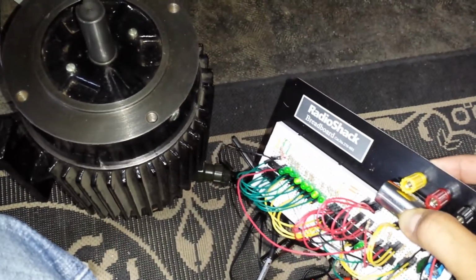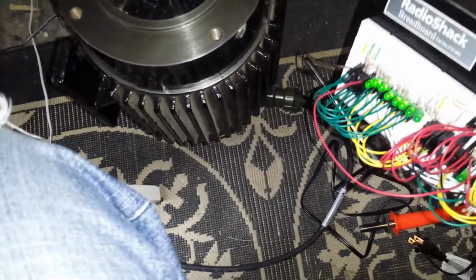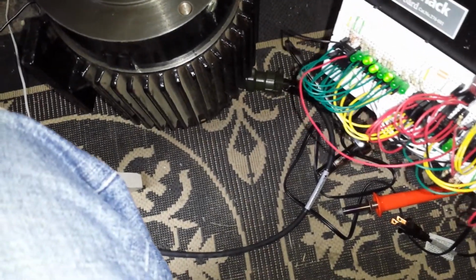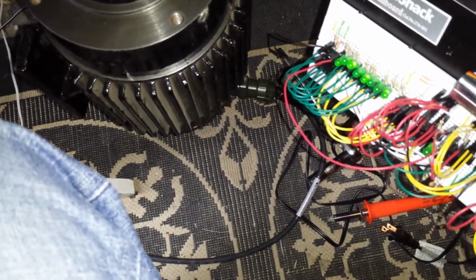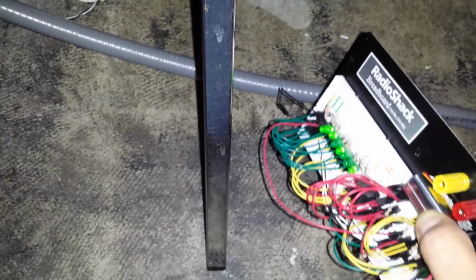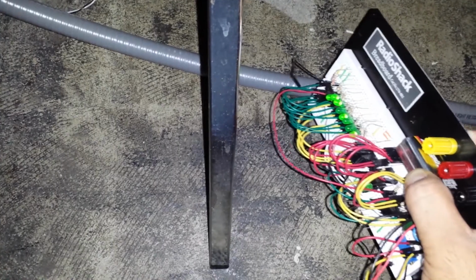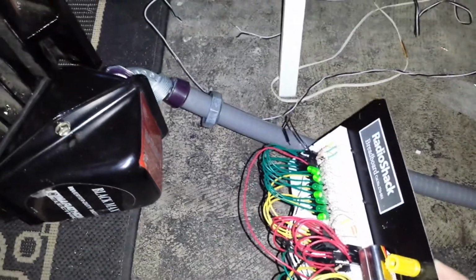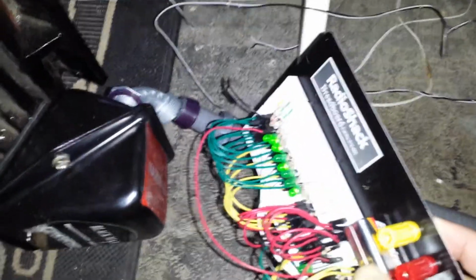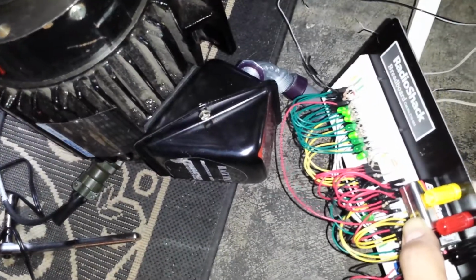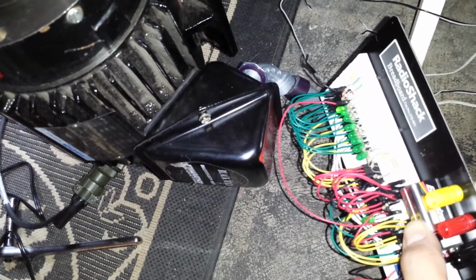And if I come over here to the motor, it is pretty bad. I can only get a couple of inches away before it starts doing that. So if I look at the actual power cables, they don't do anything. There doesn't seem to be any radiated noise coming off of there.